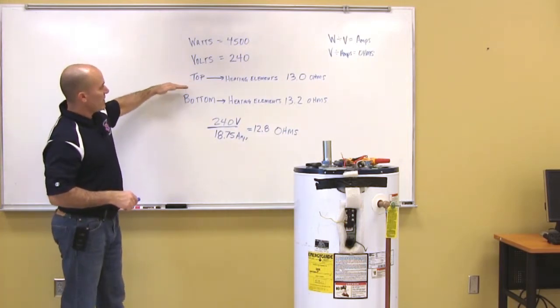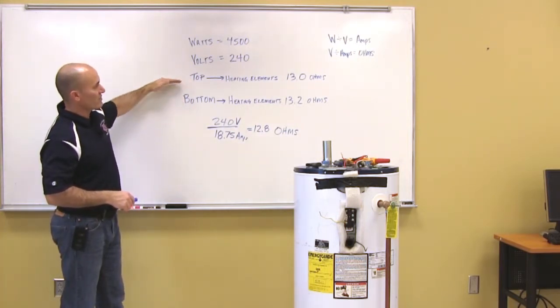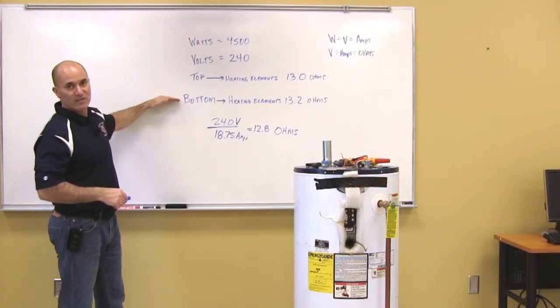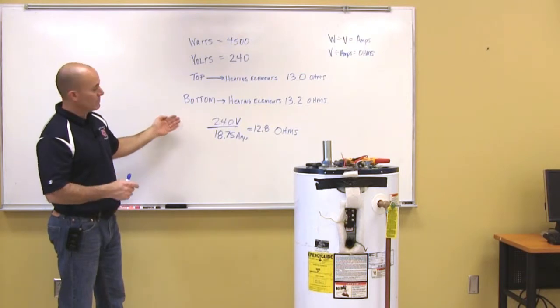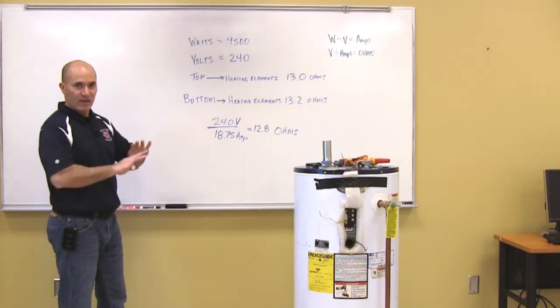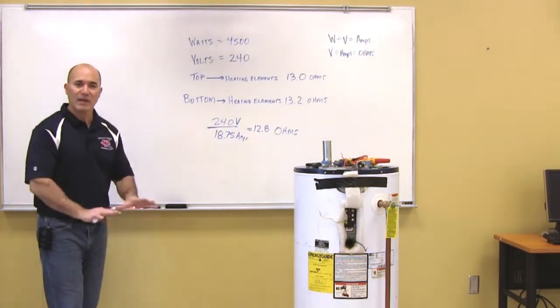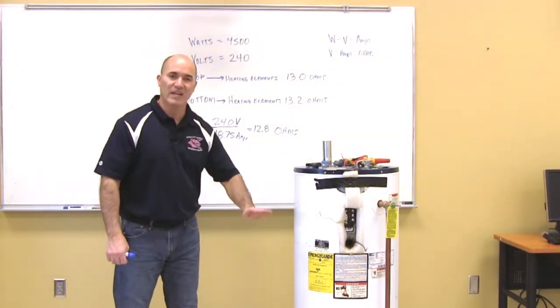So if I look at my heating elements, I've got 13 and 13.2, they're legit, they're fine. I tested them, I did the math, everything's good. So I eliminated the process of my heating elements being bad.